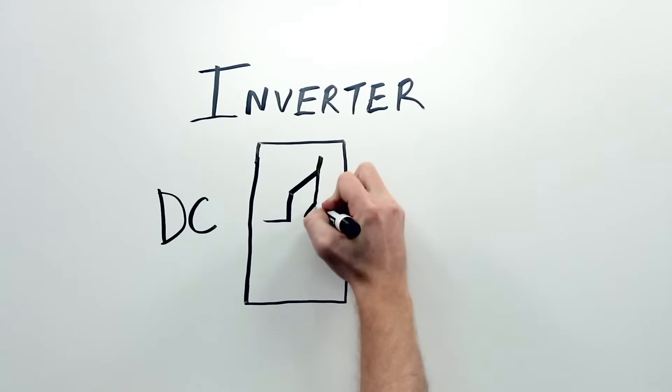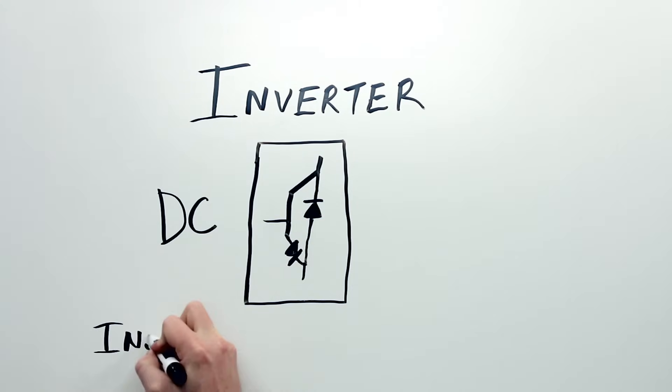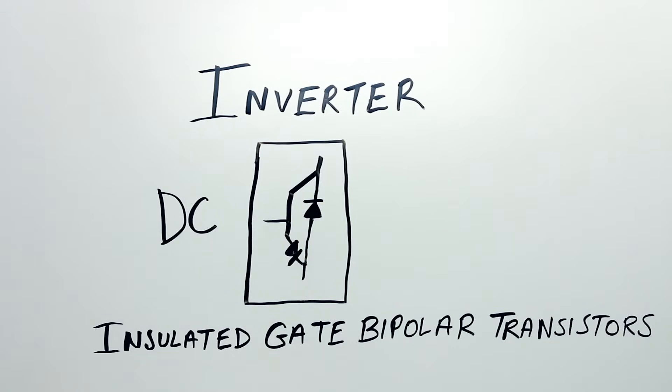Inside the inverter, there are small circuit board components called insulated gate bipolar transistors, which everyone calls IGBTs. The IGBTs act as little triggers that take the DC power and fire it out in short bursts. So the IGBTs spit out the DC in a short burst, then another, then another. Then they let out the DC a little longer, and then a little longer, and then a little shorter. Then they take the DC and flip the polarity. The DC is turned on and off, on and off, pow, pow, pow, pow.